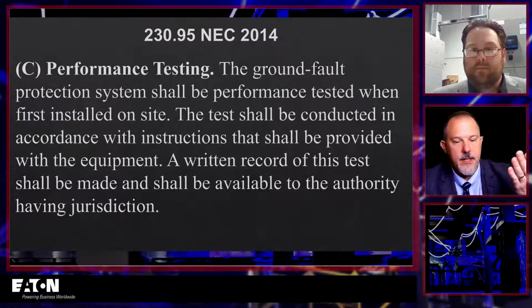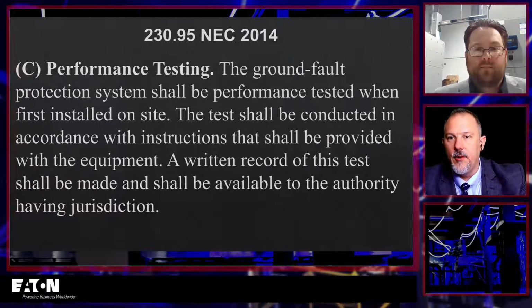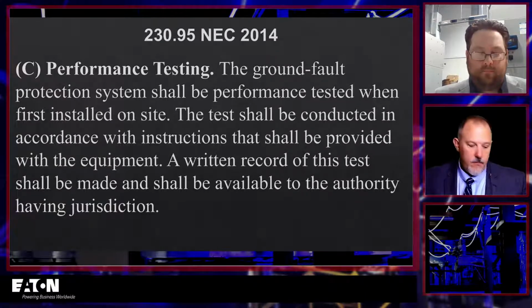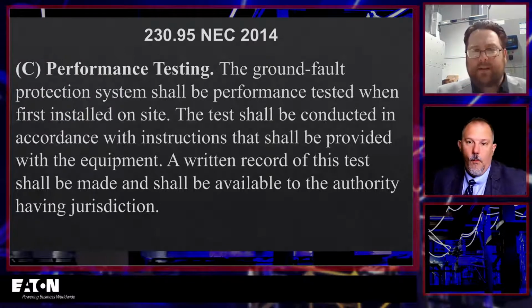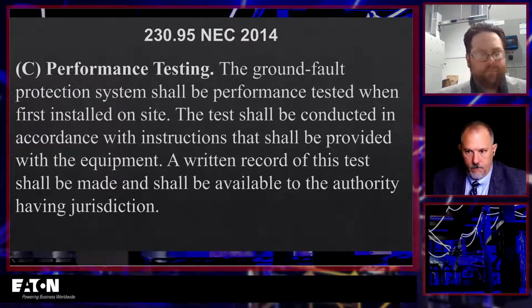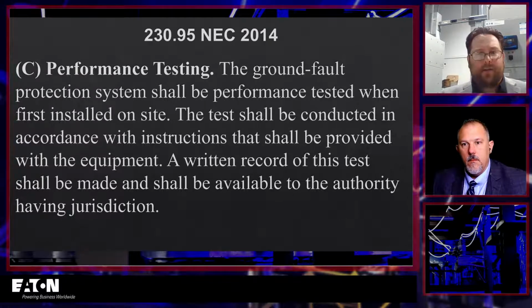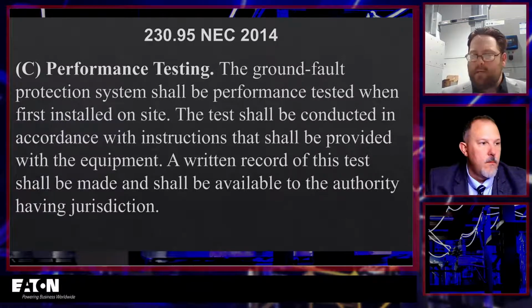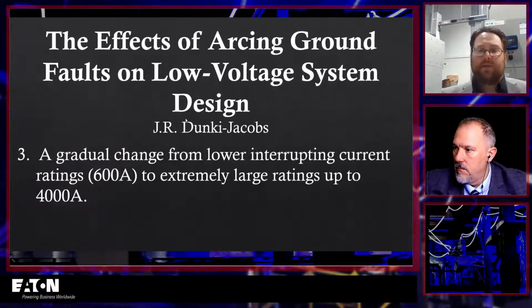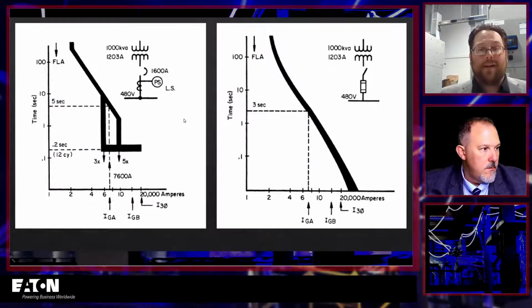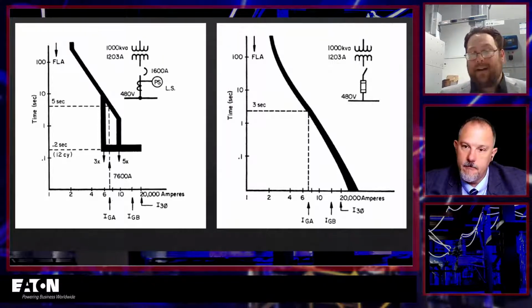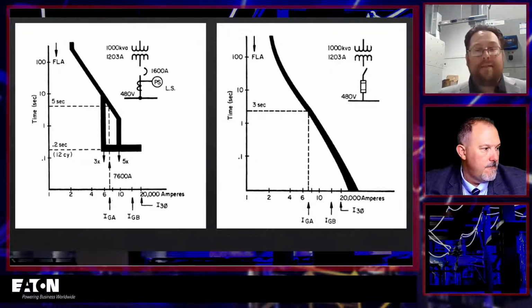And there it is in the 14 code. So this is what we're honing in on, performance testing, right? Yeah, I was going to say one thing, Tom, jumping back a little bit to those time current curves. With ground fault protection you're looking at that ground current, which is a lesser magnitude than phase current, and that has its benefits.